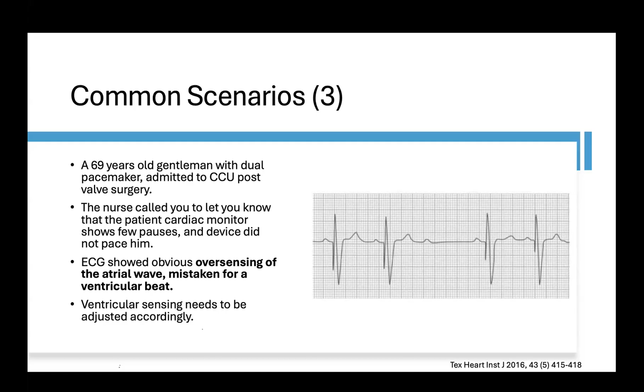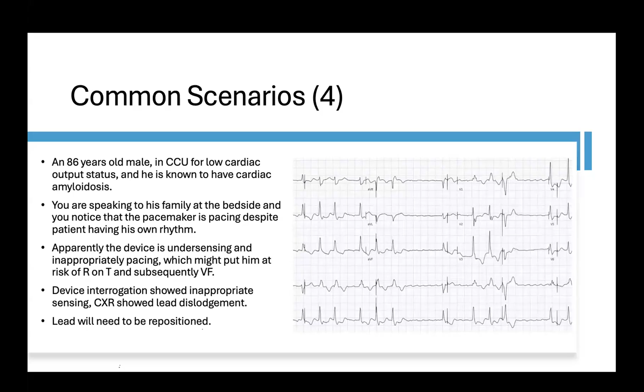Another scenario here is an 86 years old male in CCU for low cardiac output status going into cardiogenic shock. He's known to have cardiac amyloidosis. So you're speaking to the family at the bedside, and you notice that the pacemaker is at times pacing despite the patient having his own rhythm, and then at other times not pacing at all. So apparently the device here is undersensing and inappropriately pacing, which might put this patient at risk of R on T and subsequently VF. So the device interrogation showed that this sensing was inappropriate, and then the chest X-ray showed lead dislodgement. So the lead will need to be repositioned.